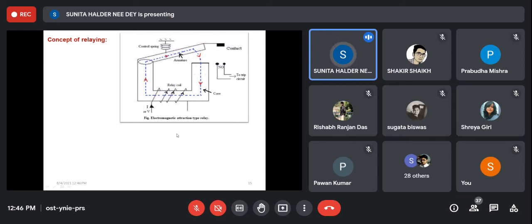And since the moving part is attracted by the fixed part, it is called an electromagnetic attraction type relay. Why electromagnetic? Because here we are providing protection by using electromagnetic induction. Now I have told you that this flux should be high enough depending on the system current so that the moving contact will move. So how will you set that? That's why there is a spring. This flux will be high enough to overcome the spring tension in the opposite direction. So this spring will keep the moving part in the open condition, and if we want to close the circuit, then this flux will be high enough to counteract the tension provided by the control spring, right?